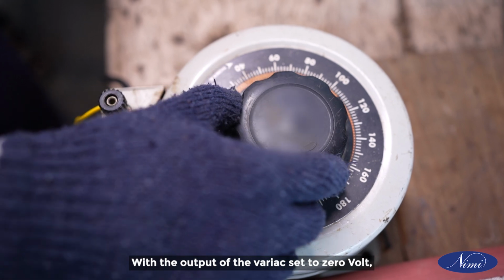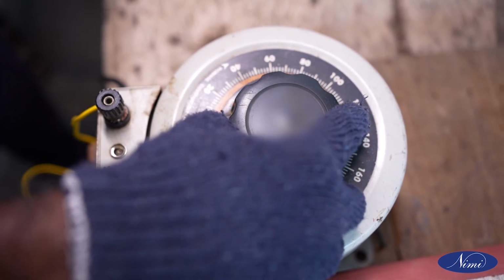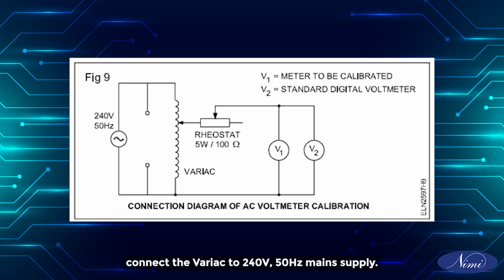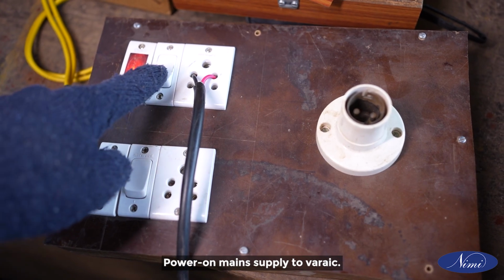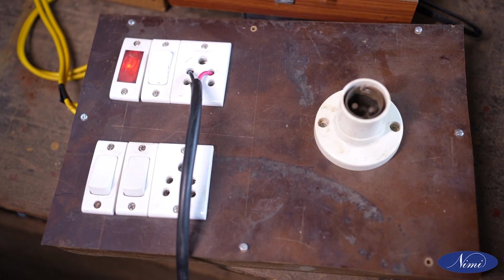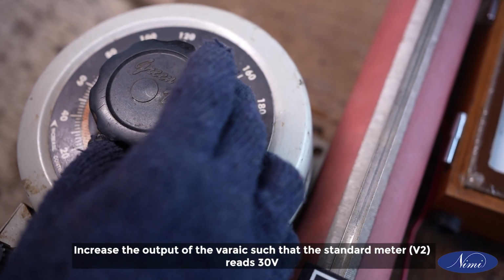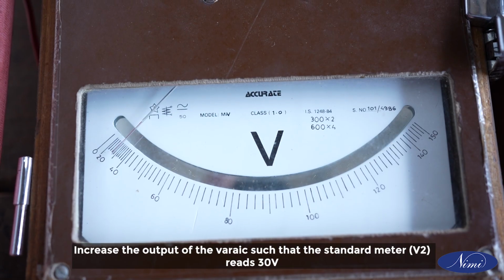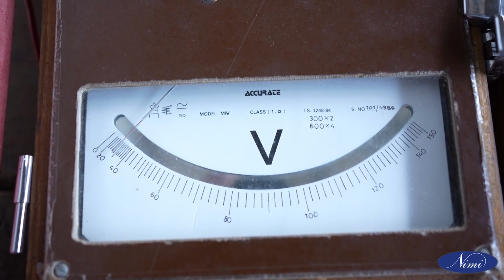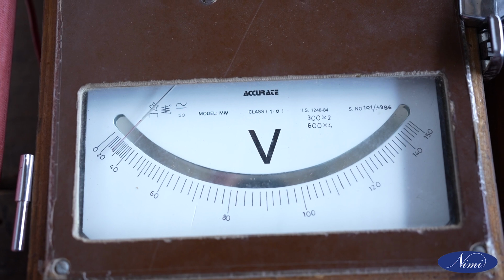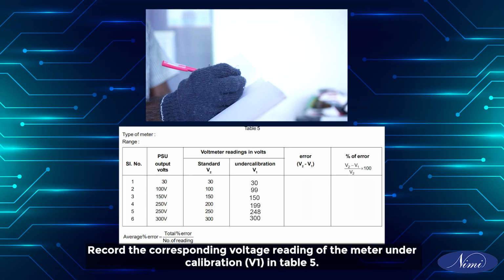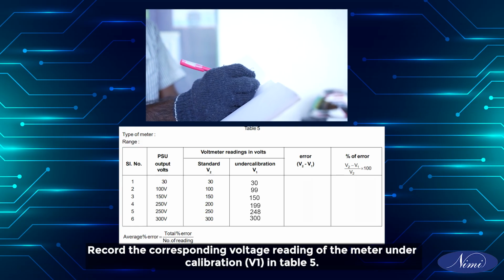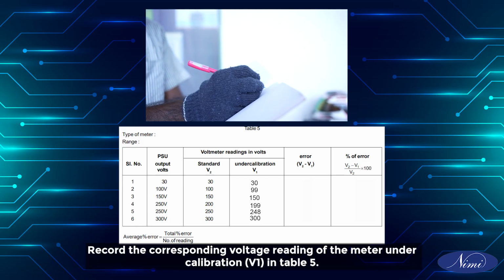With the output of the variac set to 0 volt, connect the variac to 240 volt, 50 Hz mains supply. Get the connections made checked by your instructor. Power on mains supply to variac. Increase the output of the variac such that the standard meter, V2, reads 30 volts. Record the corresponding voltage reading of the meter under calibration, V1, in table 5.